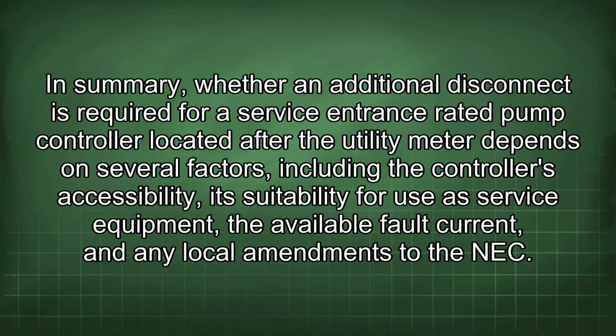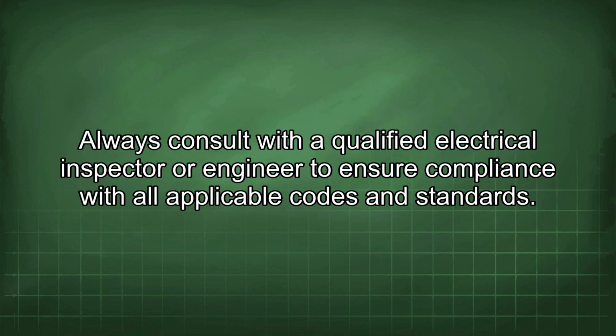In summary, whether an additional disconnect is required for a service entrance rated pump controller located after the utility meter depends on several factors, including the controller's accessibility, its suitability for use as service equipment, the available fault current, and any local amendments to the NEC. Always consult with a qualified electrical inspector or engineer to ensure compliance with all applicable codes and standards.